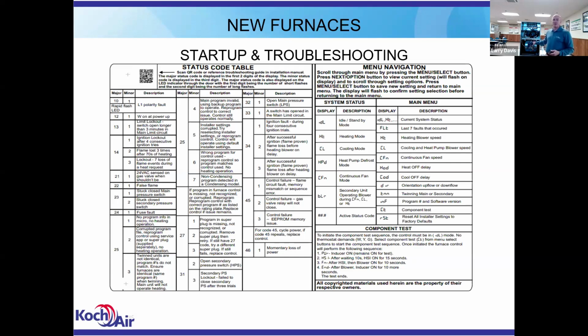On this one, like I said earlier, it's going to store those faults up to 72 hours. You're going to be able to go up to that board because you got to pull the door off to see the display. As soon as you do that, you're powering the board down. You can power back up and read your display, or you can connect to it with the app and pull the fault code up and see what's going on.